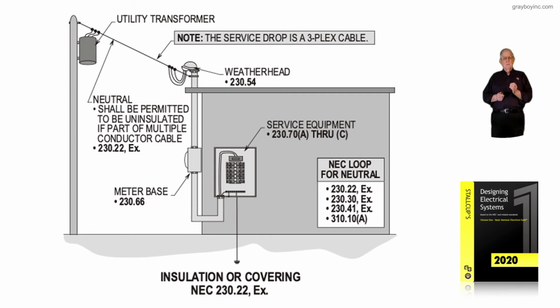And you'd say, well, no, as the designer, the neutral calculated per 220.61 is a 1/0. Then the 1/0 calculated for neutral load per 220.61 is more than adequate to serve as the path for the fault current that only had to be number 2 per table 250.102C1 based upon the 4 conductors from the weatherhead terminating to the 225 amp main in the service equipment.